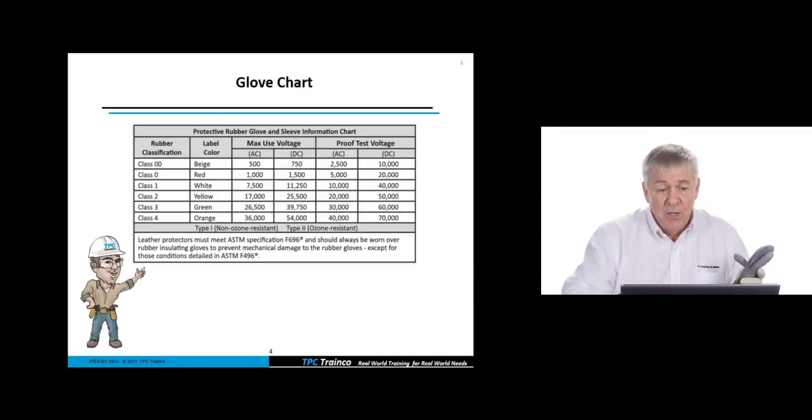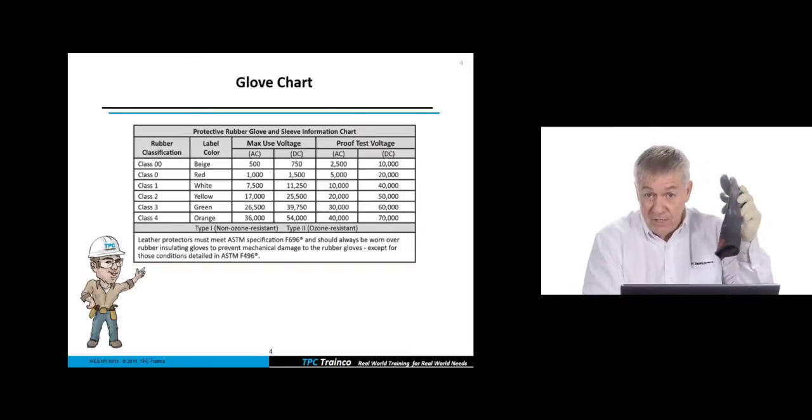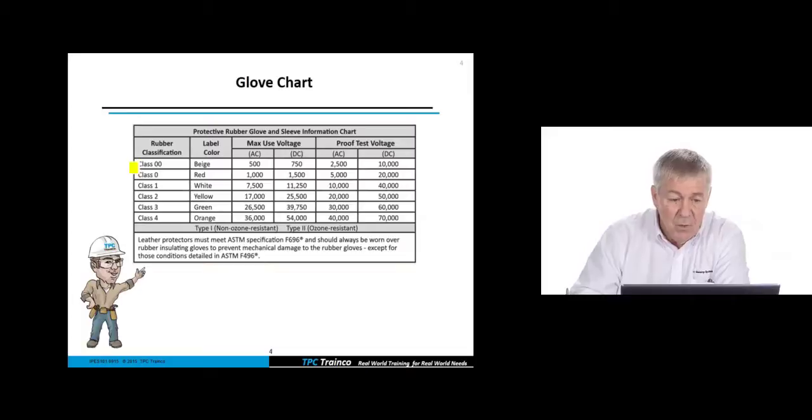But every six months, we're going to have this glove be dielectrically tested. So what does that mean? Well, that means that we're going to go, and remember I had a red label. So that means that I have a class zero glove. And when this gets to be sent out to be dielectrically tested, it's going to be tested at 5,000 volts AC and 20,000 volts DC.